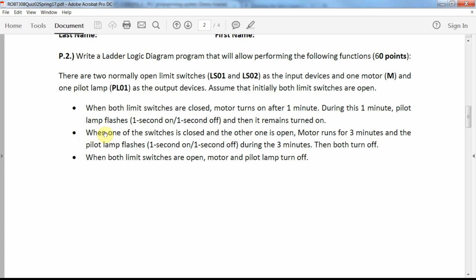The second case: when one switch is closed and the other is open — LS01 or LS02 — the motor runs for three minutes and during these three minutes the pilot lamp flashes, then both turn off. Whenever both limit switches are open, the motor and pilot lamp will turn off.